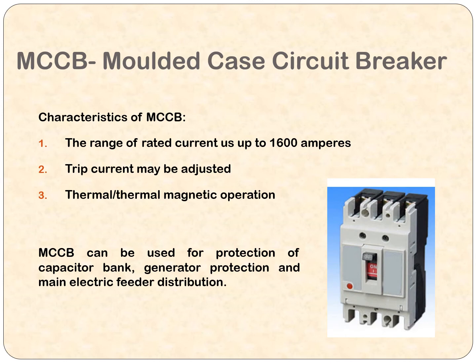So the characteristics of an MCCB are: it can be used for a range up to 1600 amps, and the trip current may be adjustable, and it has thermal and thermomagnetic operation, which is the same as MCB. The only difference is that it has more power handling capacity, 1600 amps and the corresponding voltage. So power is equal to V into I, and of course it has adjustable trip current. With these two, it is a preferable choice for generating stations and main electrical feeders, etc.